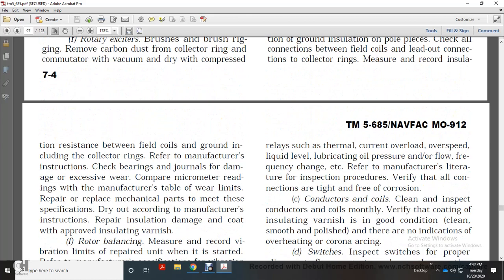Resistance between the field coils, ground, including collector rings. Refer to manufacturer instructions. Check the bearing journals for excessive wear. Compare micrometer readings to the manufacturer's table of wear limits. Replace mechanical parts that do not meet the specification. Dry out according to manufacturer instructions.